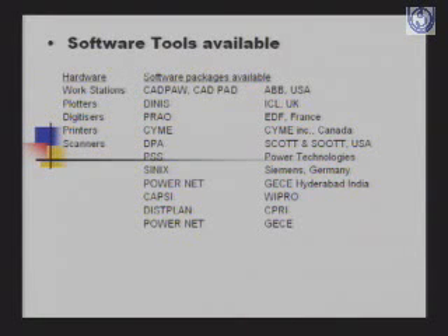To find out which is the best solution, you have to use softwares for carrying out system studies. Because the distribution system is very wide, it is not possible to carry out voltage drop calculations and loss calculations by hand. We had earlier been doing the kVA kilometer method, but it is very approximate and, with the extension of our distribution systems, it is quite tedious and very cumbersome to do it manually. So we now have software tools available to develop the long-term plans and carry out system studies, load flow studies for finding out what will be the voltage drop in each section and what will be the current in each section, and find out the total losses.